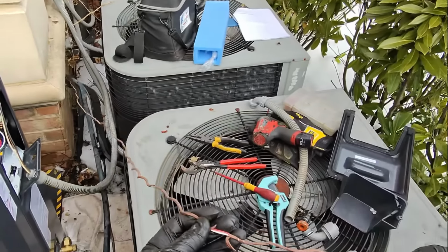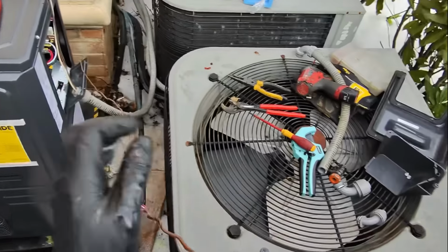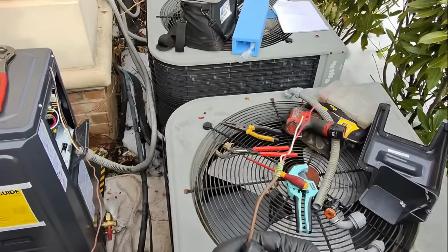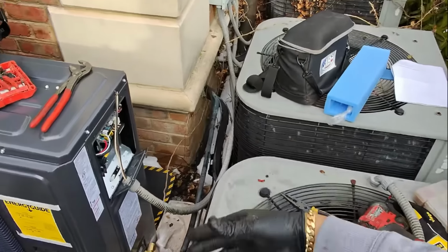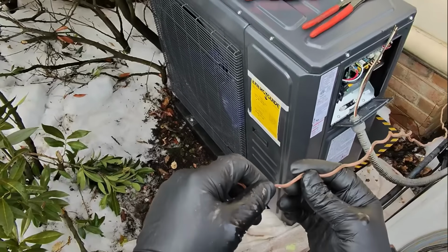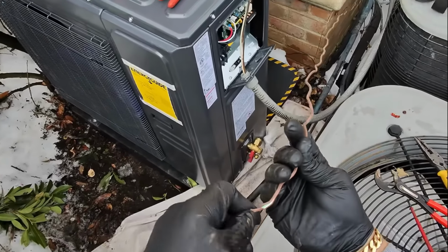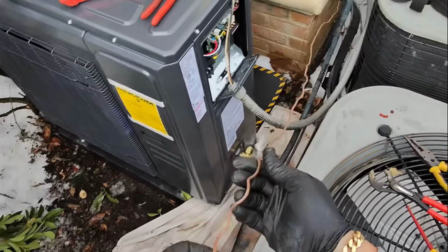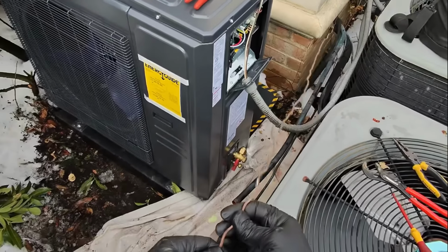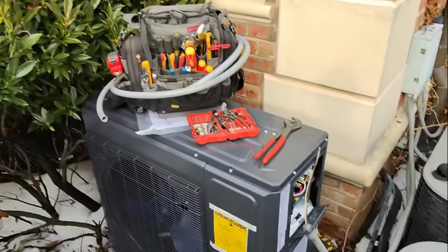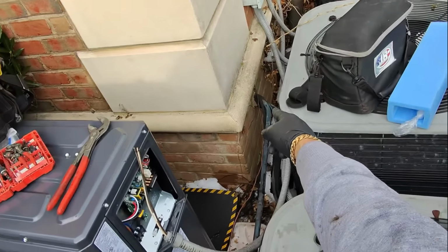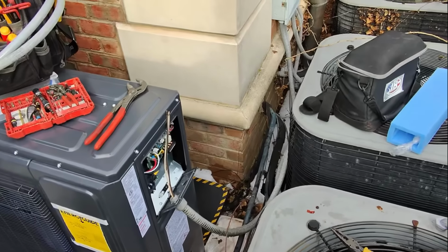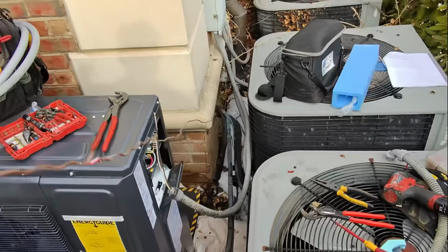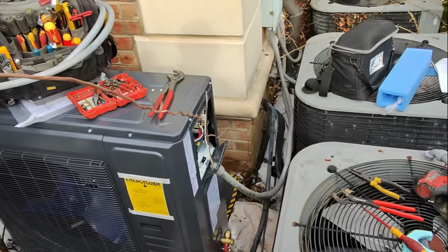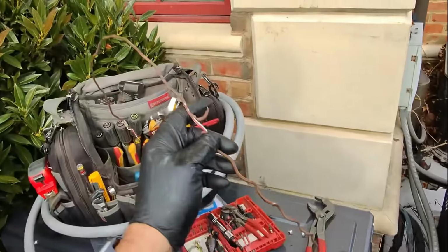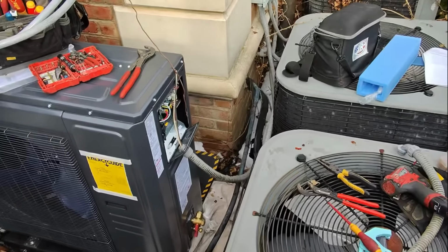Here is that low voltage communication wire that was carrying low voltage from the air handler to the outdoor unit. Unprotected, just exposed to the elements like this. You can see that the outer insulation that protects the conductors is starting to basically tear apart. So we're going to cover this with some 1/2 inch liquid tight. I got it right there. We're going to try to maybe put some putty there and connect that right there to our outdoor unit. So just a little tech tip. Don't leave the wire exposed. Protect it from the weed whackers, animals, the elements, the sun, the ultraviolet light. Protect it, and you'll do a more professional job for your end user, your client.